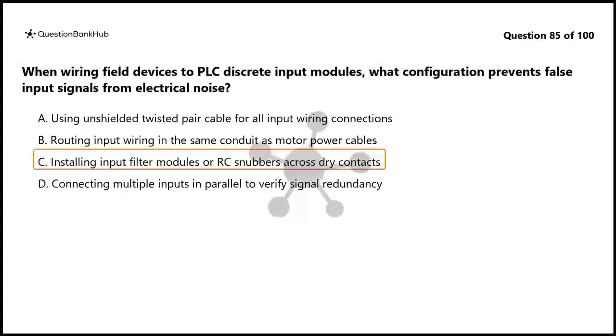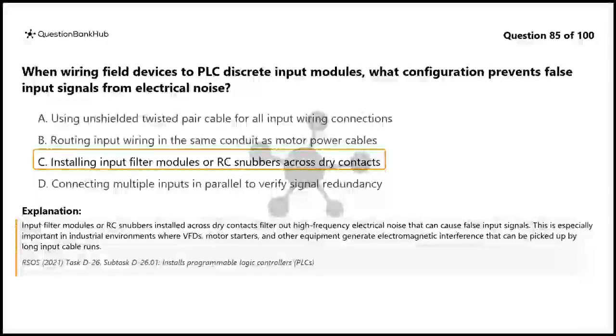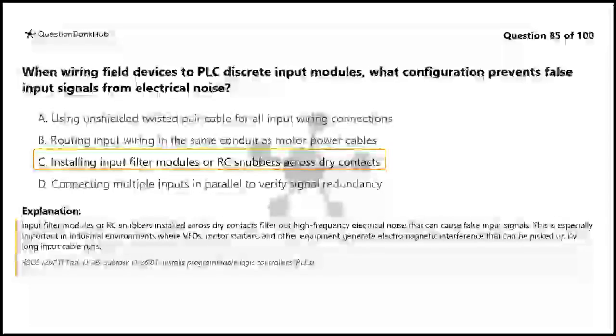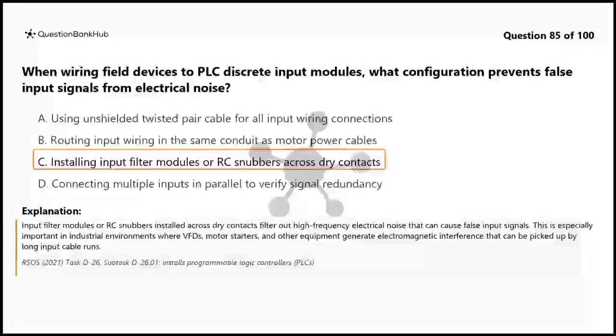The correct answer is C. Installing input filter modules or RC snubbers across dry contacts. Input filter modules or RC snubbers installed across dry contacts filter out high-frequency electrical noise that can cause false input signals. This is especially important in industrial environments where VFDs, motor starters, and other equipment generate electromagnetic interference that can be picked up by long input cable runs.